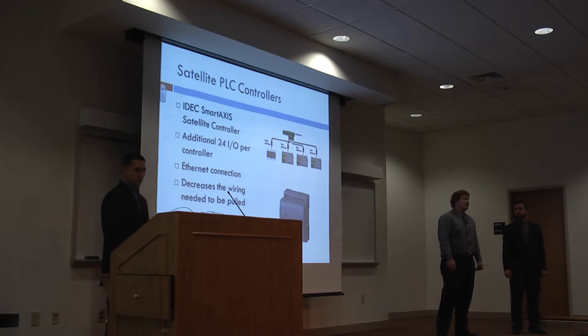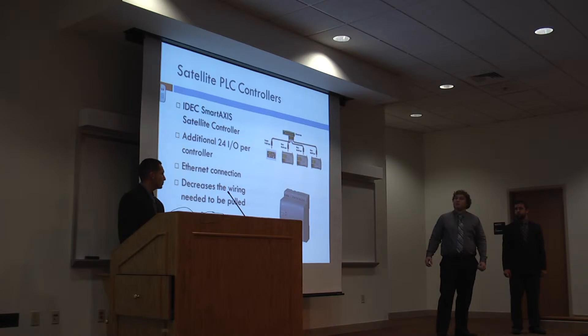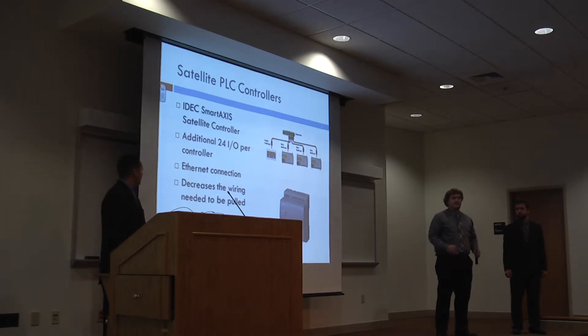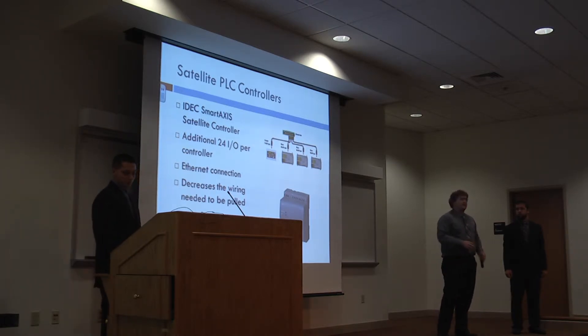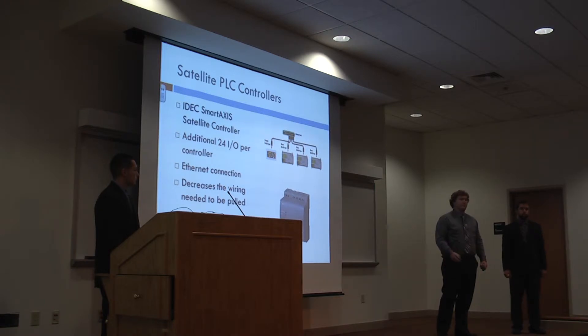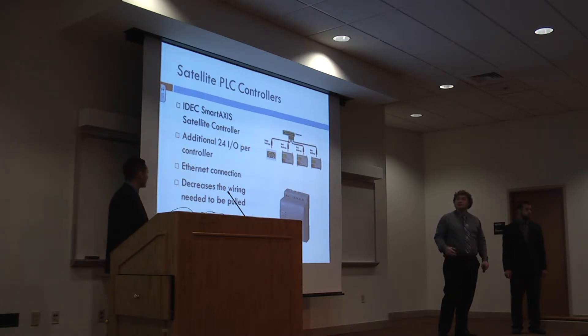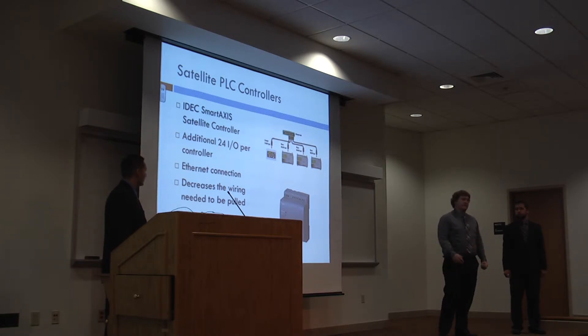For the satellite PLC controllers, we also went with the IDEC SmartAXIS. It doesn't have an HMI — it is just the PLC. It has 24 additional inputs and outputs per controller. We used the 24 to allow for more capacity if anyone ever needs to add something else to the design. They also hook up by ethernet, which allows for easier installation and decreases the wire that needs to be pulled when they are installed.